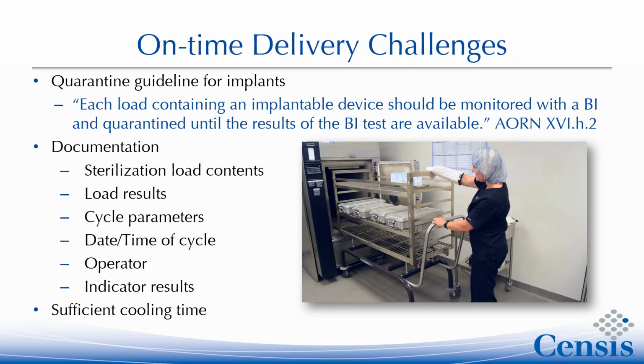Other factors that impact reprocessing efficiency include the time it takes to physically log everything going into a sterilization load, and the time needed for the load to cool properly after the cycle completes. Again, if you rush the cooling time, you can end up with wet packs, meaning the sterilization process has to be repeated.